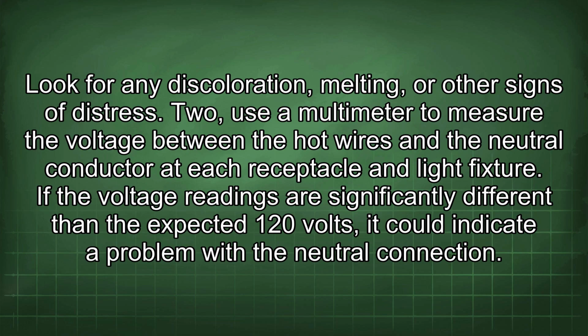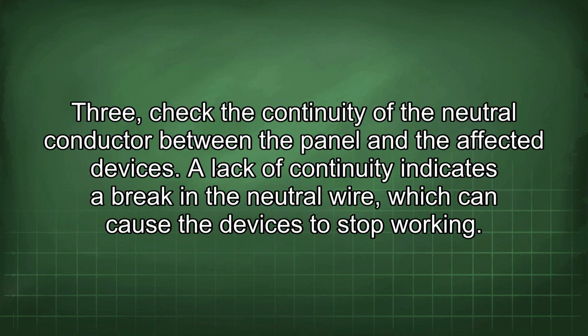2. Use a multimeter to measure the voltage between the hot wires and the neutral conductor at each receptacle and light fixture. If the voltage readings are significantly different than the expected 120 volts, it could indicate a problem with the neutral connection. 3. Check the continuity of the neutral conductor between the panel and the affected devices. A lack of continuity indicates a break in the neutral wire, which can cause the devices to stop working.